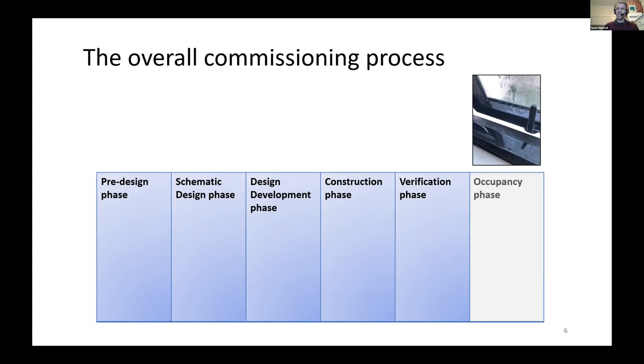Occupancy phase is sometimes when the builder or the homeowner moves in and then says, oh, actually... This is a picture from a building near Sydney, which had massive condensation problems because there was not enough ventilation, too airtight, no ventilation, and massive problems because they had a very poor building envelope. That's not the kind of commissioning you want.